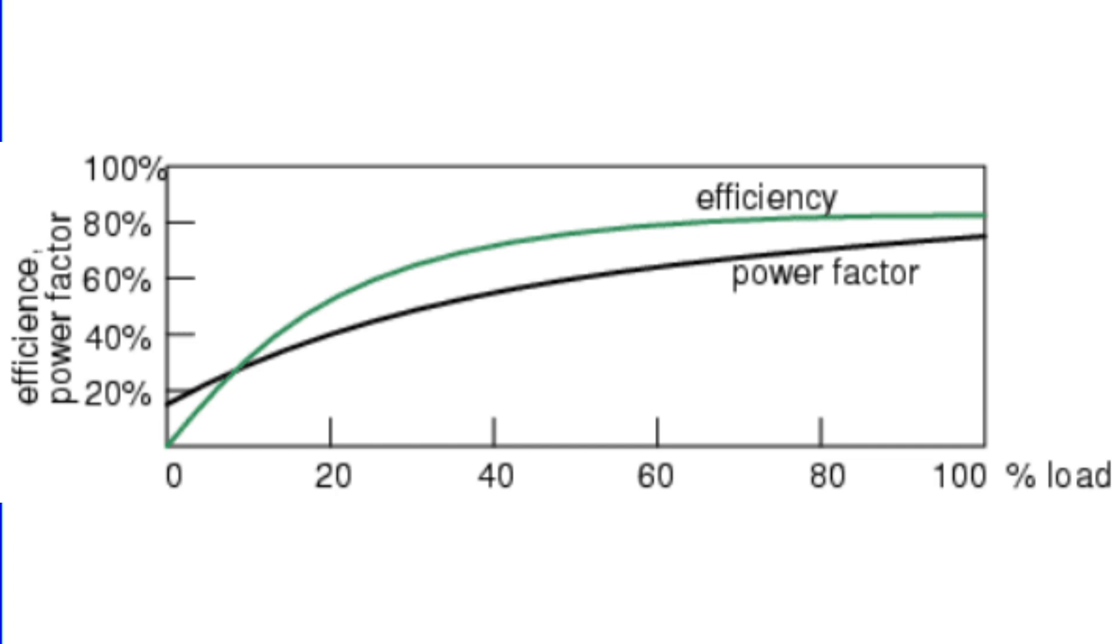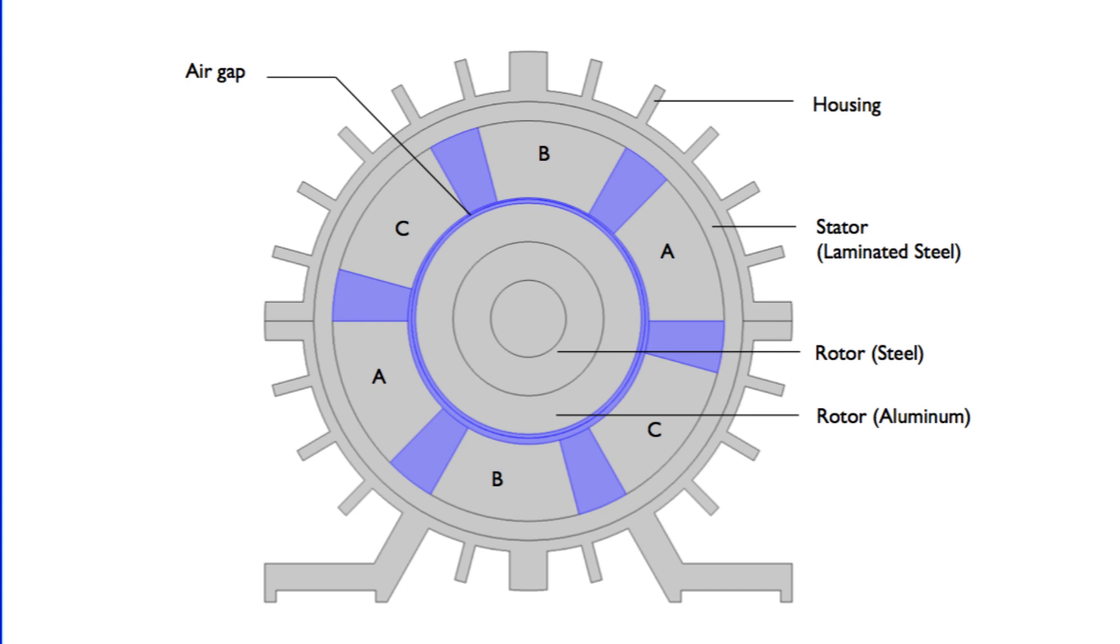As the load increases, the power factor improves. The design of the motor also plays a role. Things like the air gap between the stator and rotor can influence the magnetizing current and in turn, the power factor.